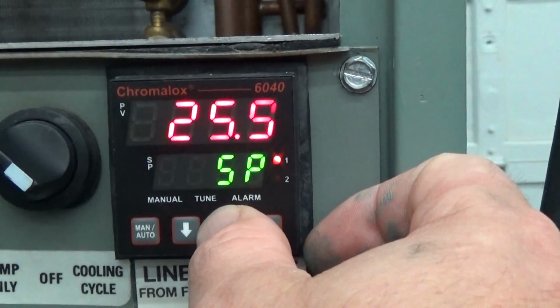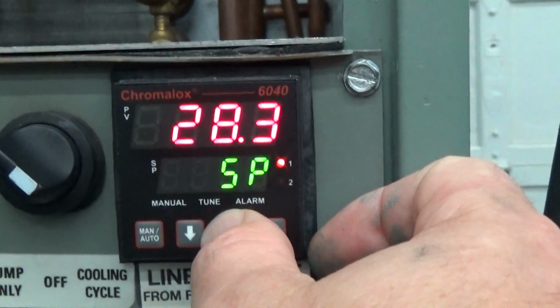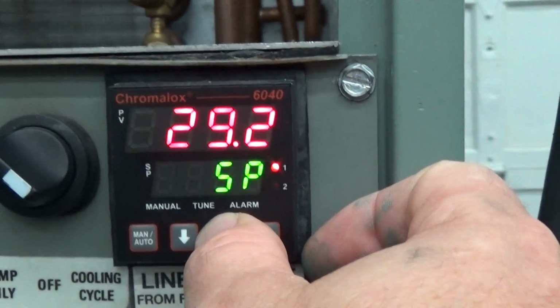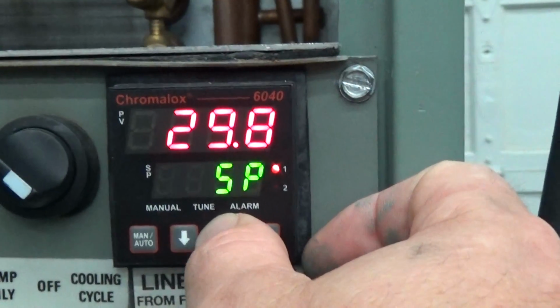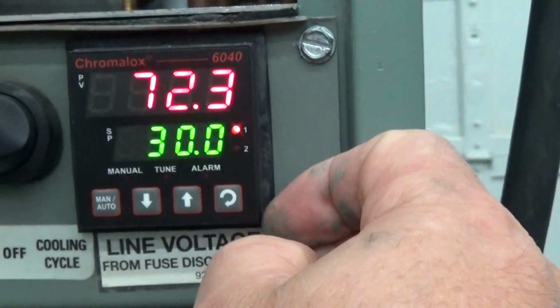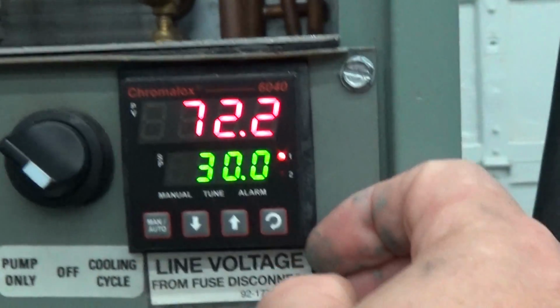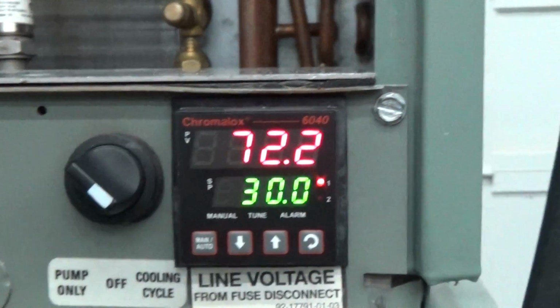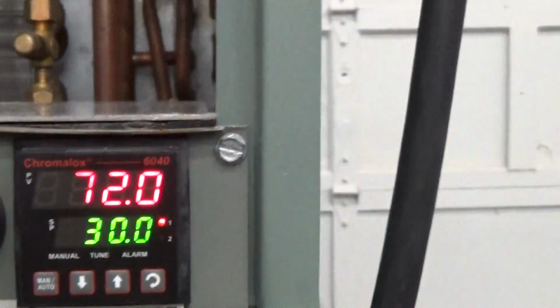I overshot a little bit, so you can tell it's real time. The compressor already kicked in. We're starting to chill. So we're going to bring it down to 30. Enter, and it just defaults back to that screen. So my set point's 30, and we're starting to chill.